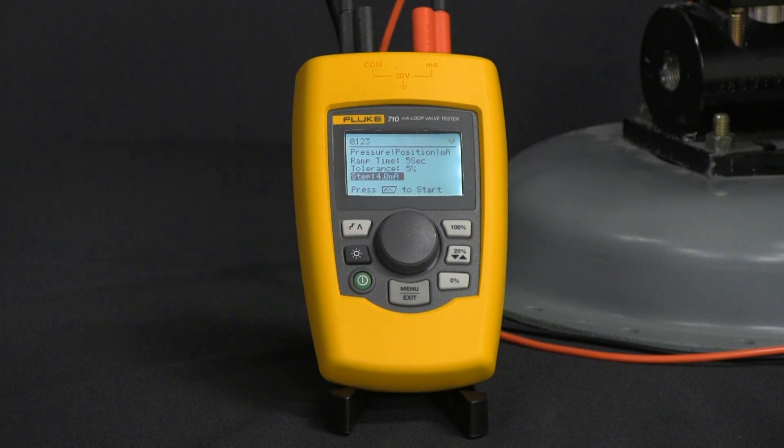Okay, from here we can set our ramp time, tolerance, and step milliamp value. Right now we have it set for five seconds ramp time, tolerance of five percent, and step is going to be four milliamps.